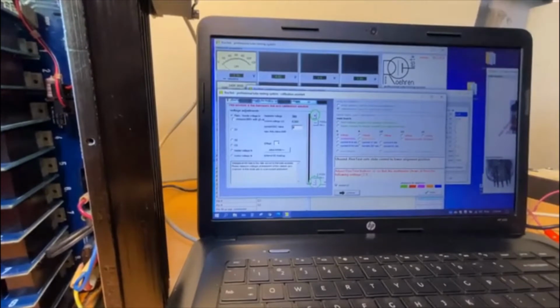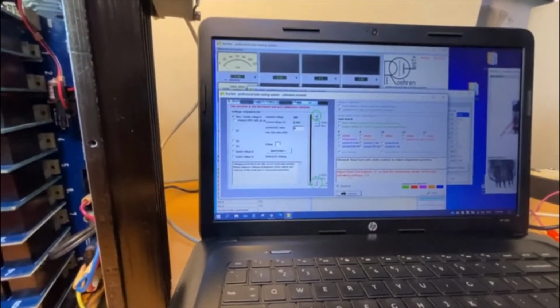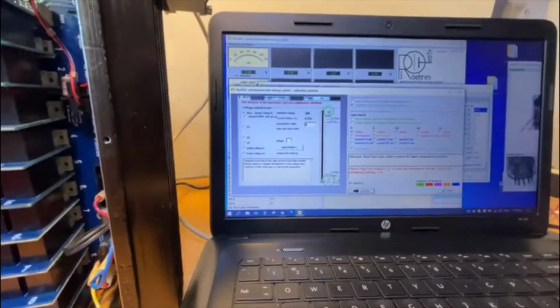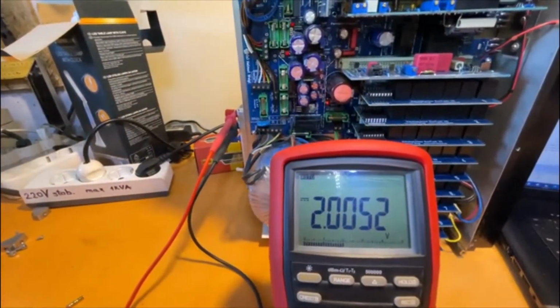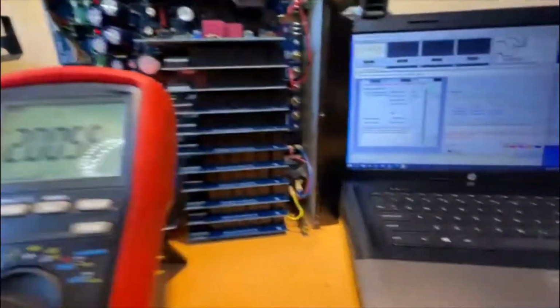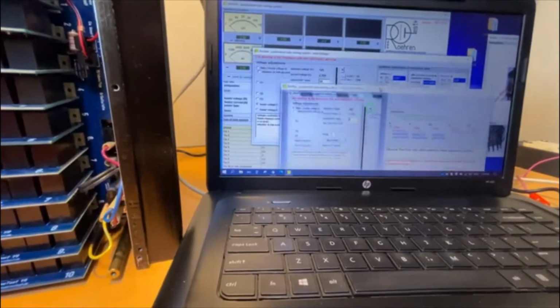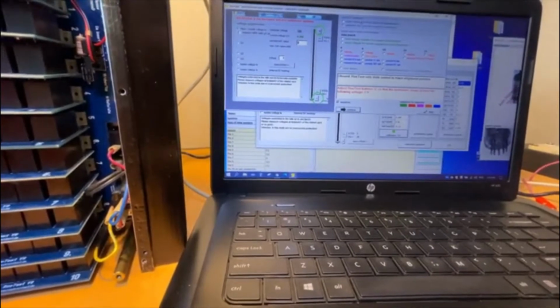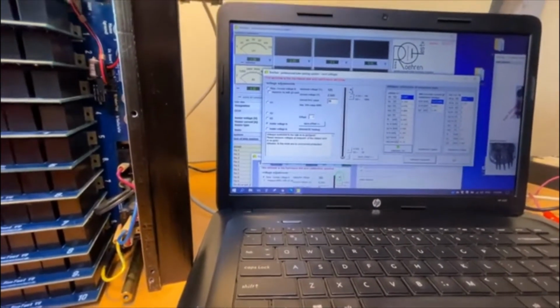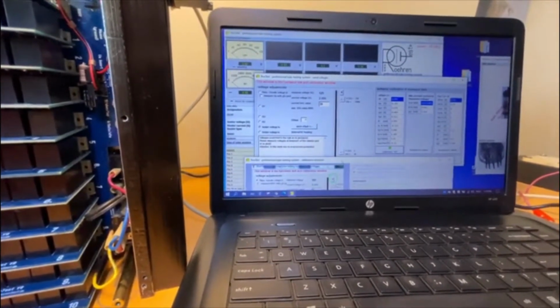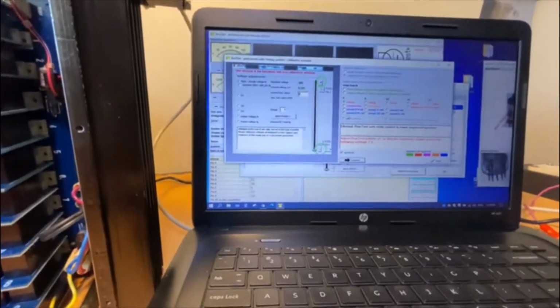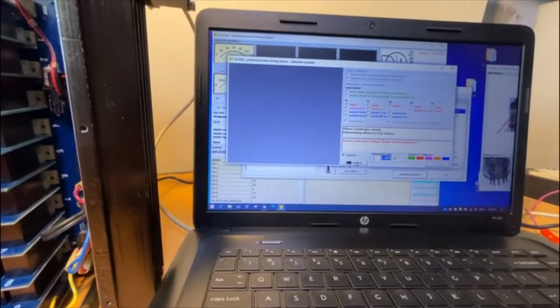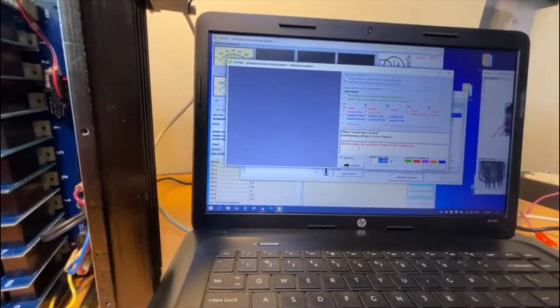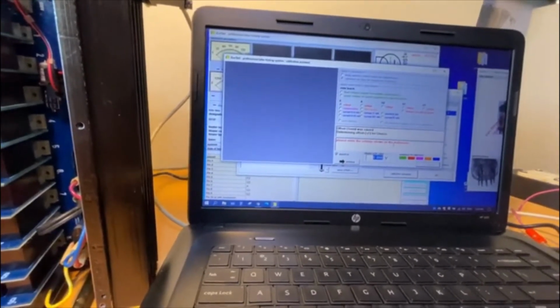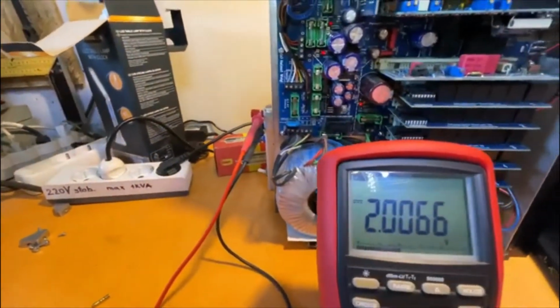It says adjust the ROETEST button so that the multimeter shows the closest value to 2 volts. The multimeter shows us 2.0055, which is excellent. We don't touch anything, or else we should work from this slider, plus, minus, and plus. Adjustment must be made from this, but it is good by calibration. Continue. Please enter the voltage shown on the multimeter. 2.0060.